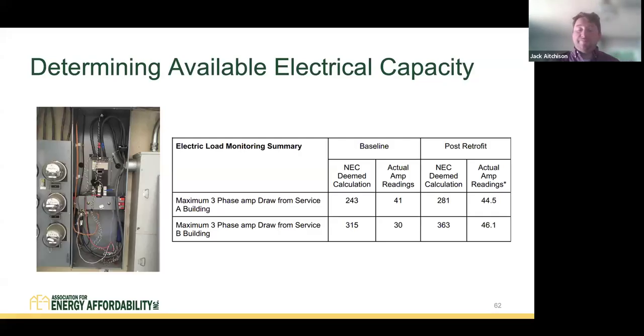post retrofit. And so you can see here in this first column, NEC deemed calculation. This is basically the result of calculating the existing electrical load based off of the calculator that is in the electrical code. And we're seeing for building A, 243 amps, for building B, 315 amps, still quite a bit of capacity compared to the 400 amp service. But if we compare that to what we actually monitored, we were seeing only 41 amps for building A and only 30 amps for building B.